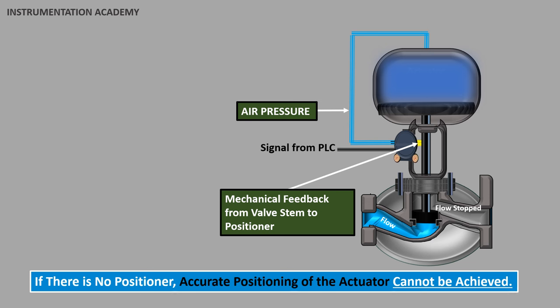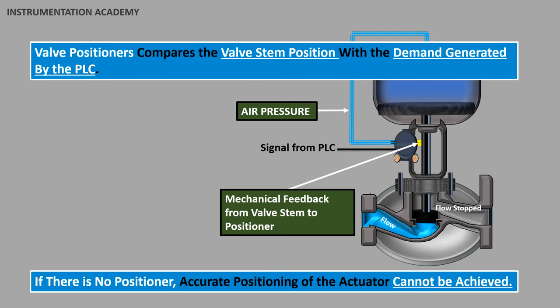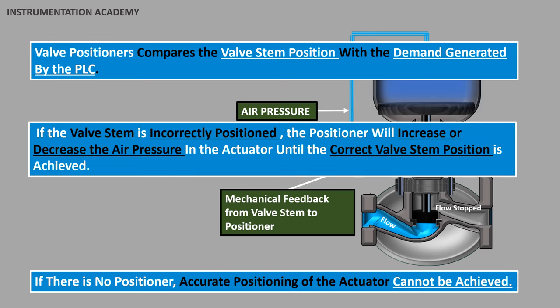The valve positioner compares the valve stem position with the demand generated by the controller like PLC. If the valve stem is incorrectly positioned, the positioner increases or decreases the air in the actuator until the correct valve stem position is achieved.